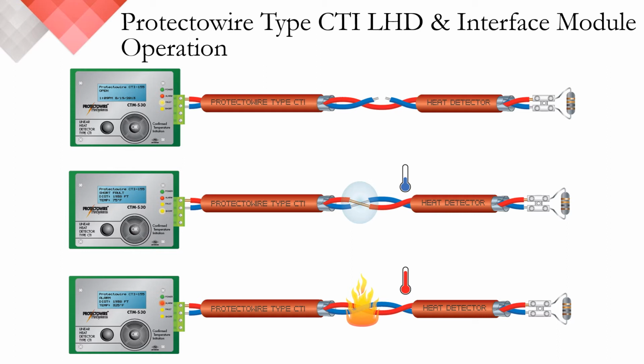Both pre-action, as well as the double interlock pre-action systems we discussed earlier, require an initiating device to function. When using our CTI series detector with a pre-action system, it significantly reduces the possibility of water being released into the pipes without a heat event. When using our CTI series detector with a double interlock pre-action system, even with a low air condition, mechanical damage to the detector does not release water into the sprinkler pipes. Mechanical damage only initiates a short fault or trouble condition.